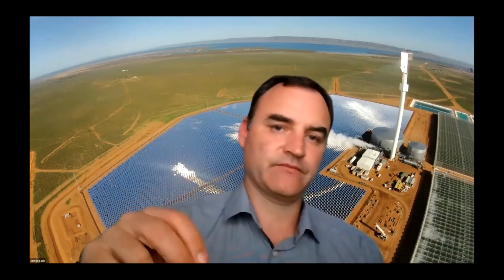The COPs we were talking about when Cordin was presenting were just on the heating side, not putting any value on the cooling that was potentially being provided. That can almost double the COP, not exactly, but that's effectively what happens when you get to the nirvana, your COP is just about doubling to 10 or so. Yeah, around 9 or 10 is what we're looking at modelling at the moment. And from what we're seeing, heat pumps are certainly viable at COPs much lower than that.